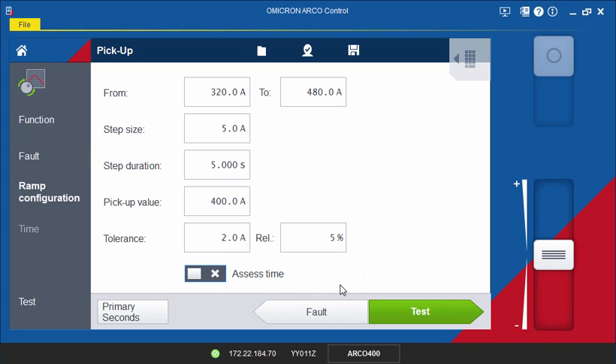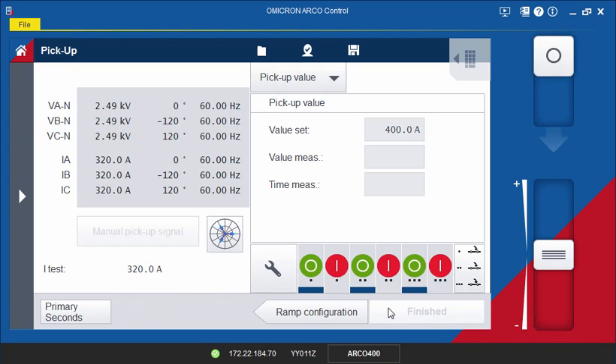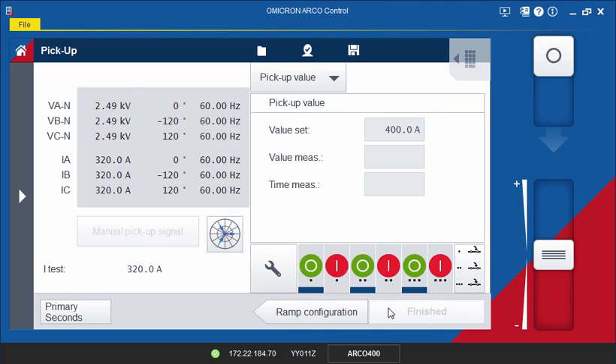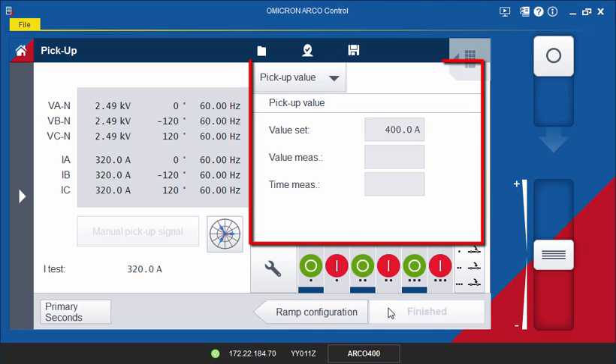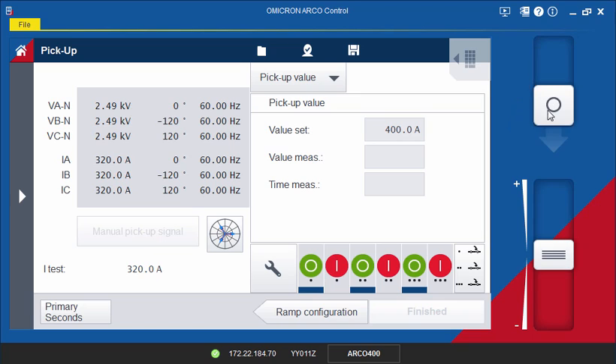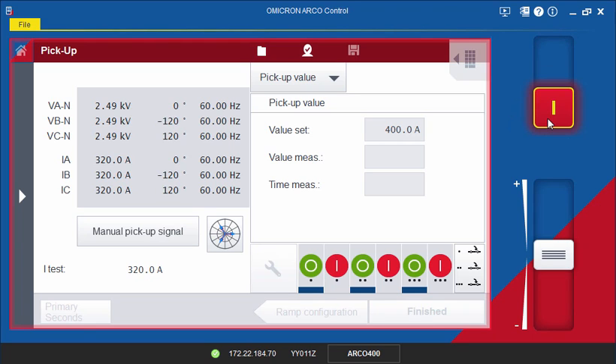Now, you can proceed directly to the test screen. On the left, you can see the output values. On the right, the events and results will be displayed. Start the test. As you can see here, the test current is increased at the defined amplitude and time steps.